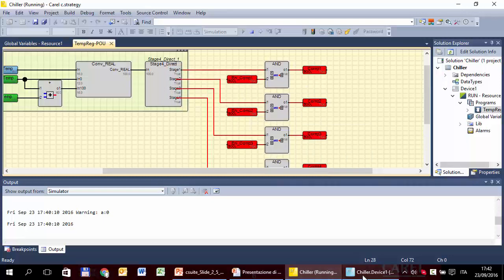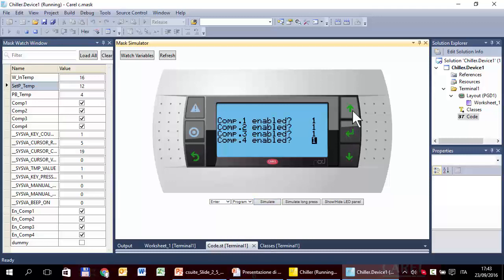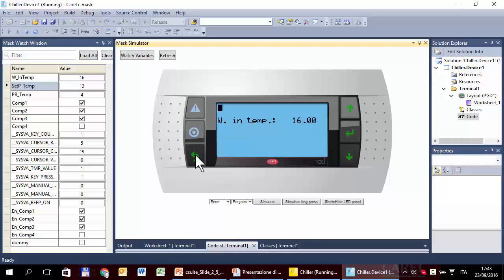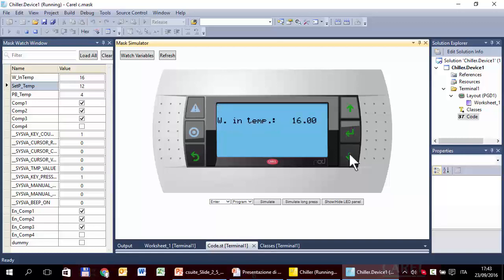Now we can check what happens if we disable the compressors. Enter again in the configuration mask. Let's disable the last one — compressor four. We expect two things: first, not to be able to enter the mask of the fourth compressor — one, two, three. In fact, the mask for the fourth compressor is invisible. So this works. Second, we expect the compressor relay to be off — the variable representing the status of compressor four is off or zero.